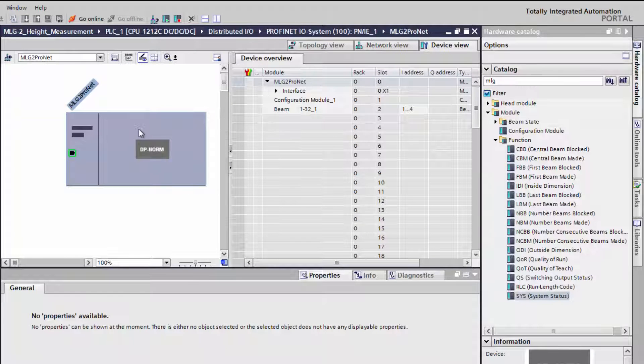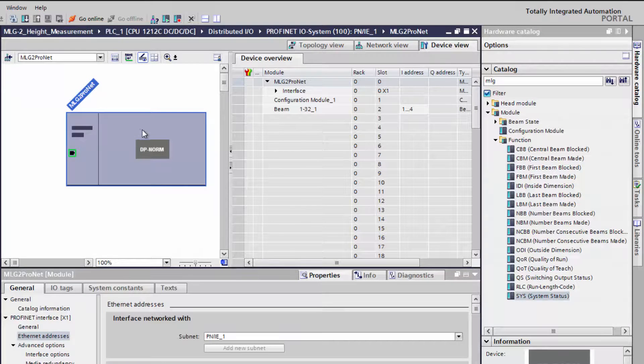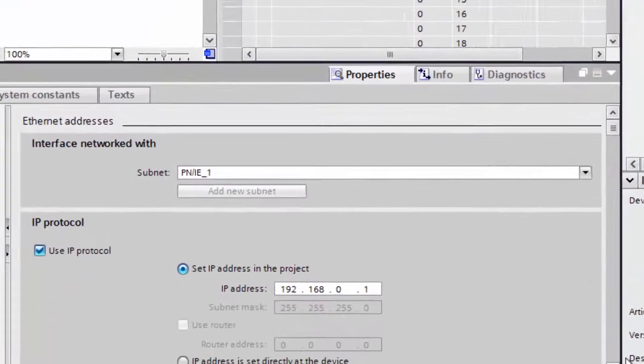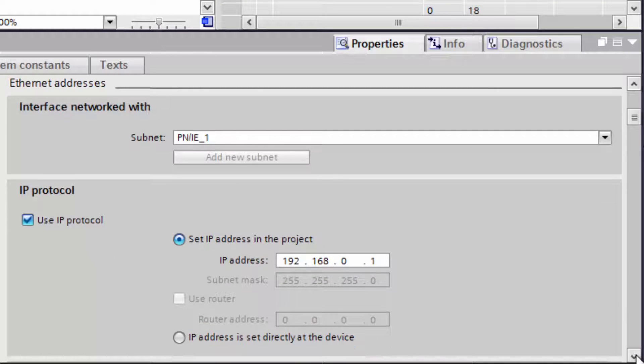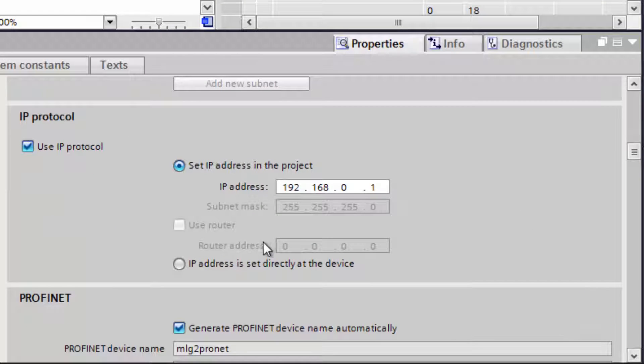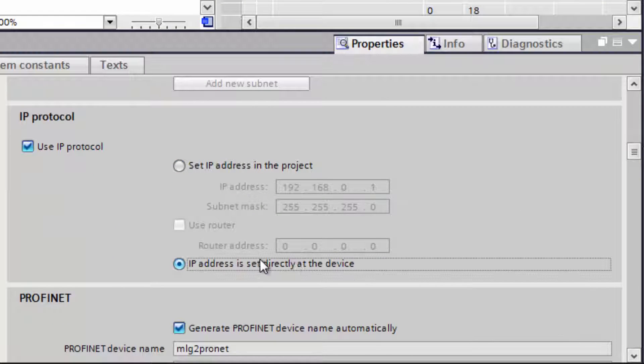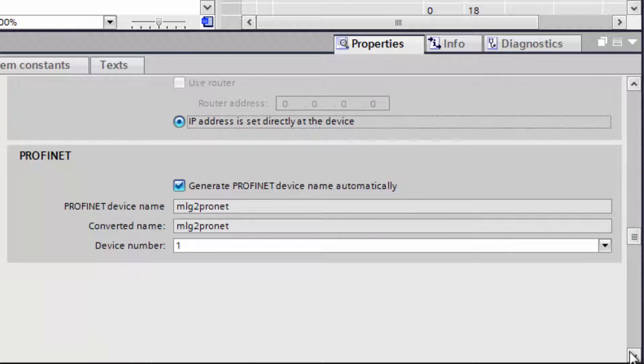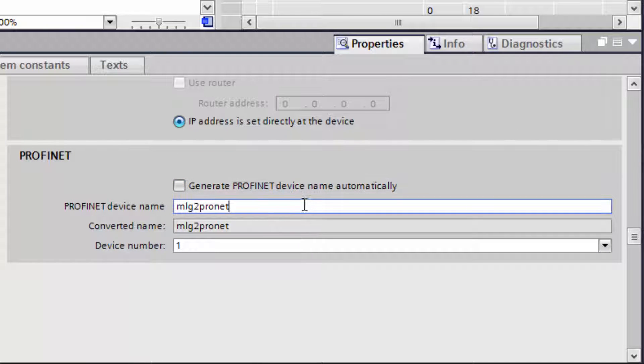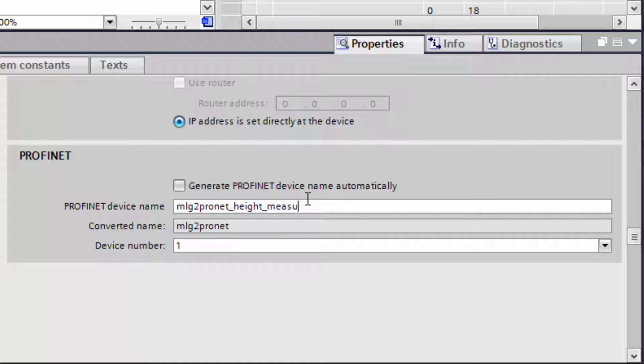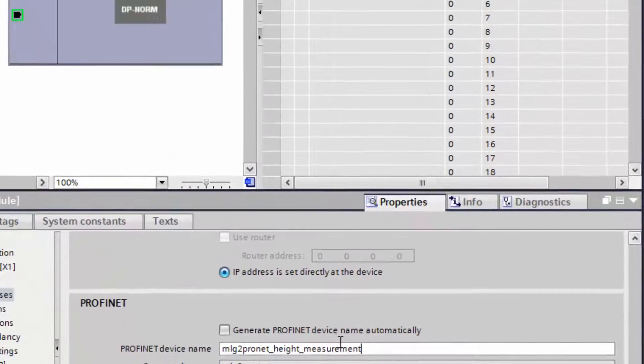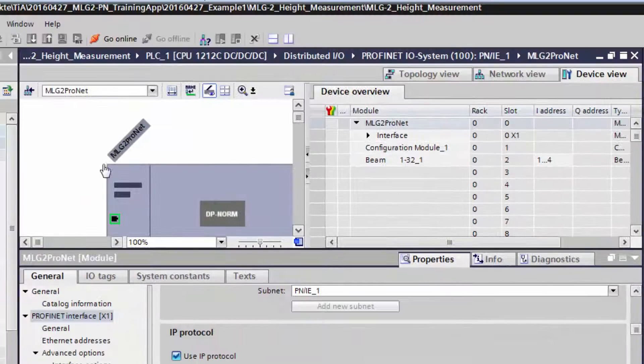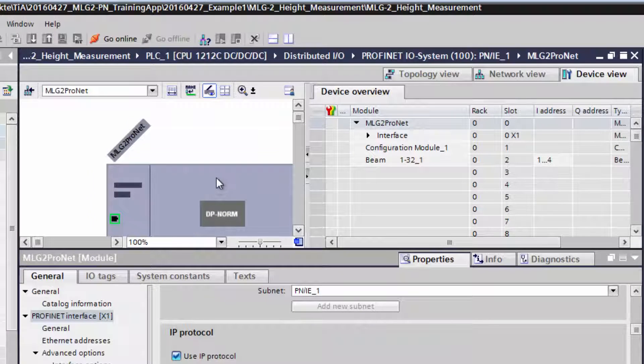Select the LightGrid's properties by double-clicking on the device. Select the item IP address is set directly at the device. Untick the box for automatic name generation and type in the correct PROFINET name, which is the previously set name MLG2_ProNet_Height_Measurement. The network settings are done now.